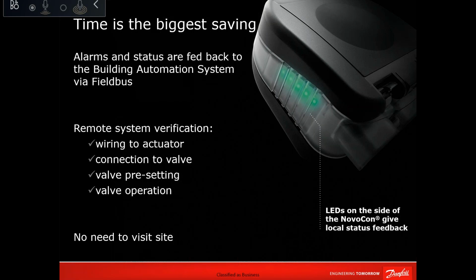It's based on the distance between the main central plant and the ETS room, or the size of the building itself, because I know in some district cooling providers there are buildings using district cooling with 7 floors, with 10 floors. Those buildings really have no big need for a PLC. It can directly be standalone controlled by a Novocon and a large ABQM valve. So yes, we have the full range from the smallest to the biggest. All actuators are available for all valve sizes.